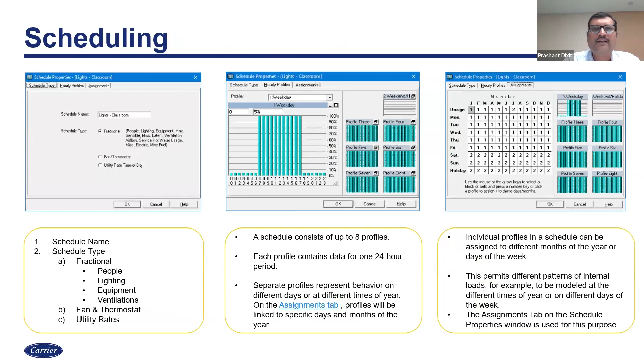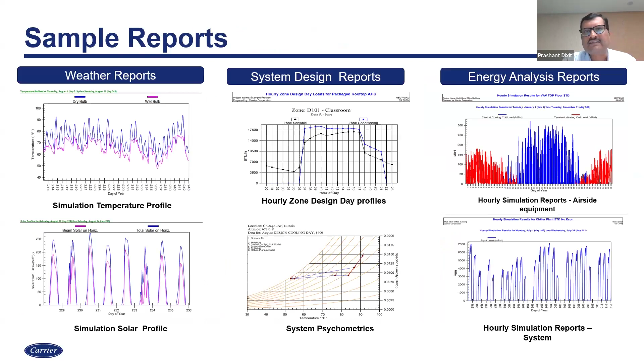Most importantly, about scheduling - when you do this scheduling properly, you don't have to consider the diversity factor because you've already accounted for all possible room occupancies and plugged those loads properly. So it gives multiple reports like weather reports, system design reports, energy reports. By doing all these things, you can reduce the demand. When we say reduce demand, the intent is not to reduce the plant room and make the clients suffer - it's to right size the building using scientifically proven tools.